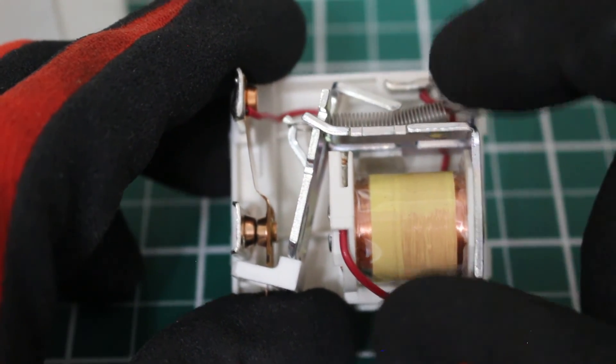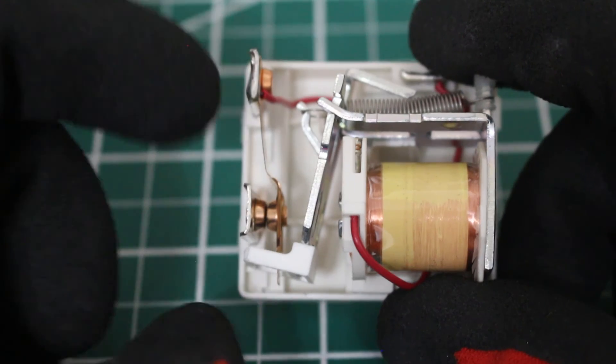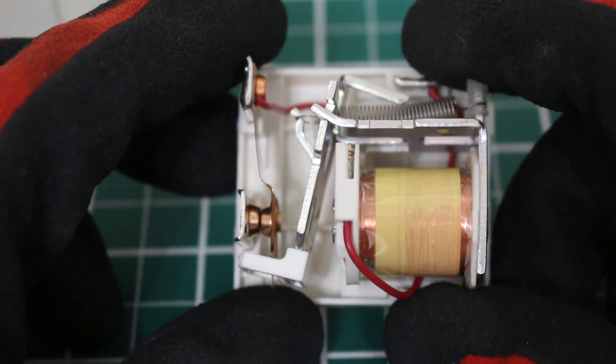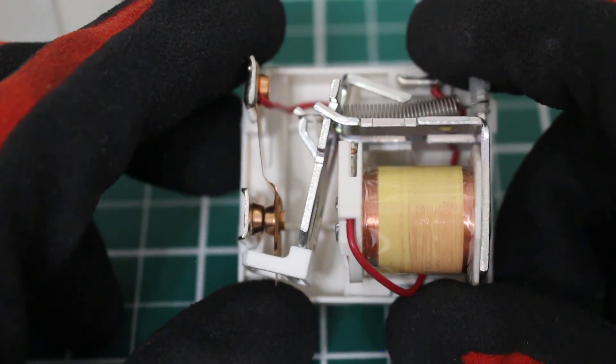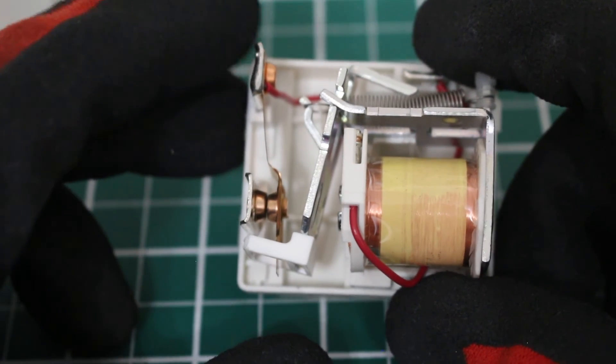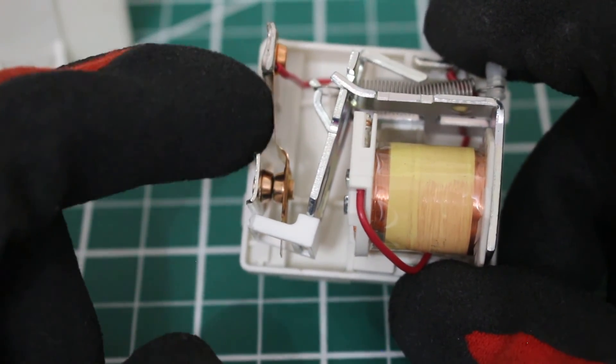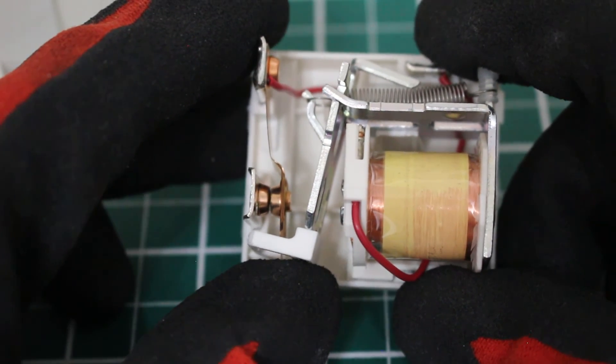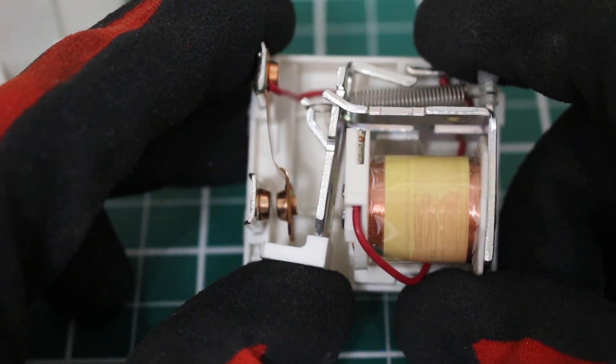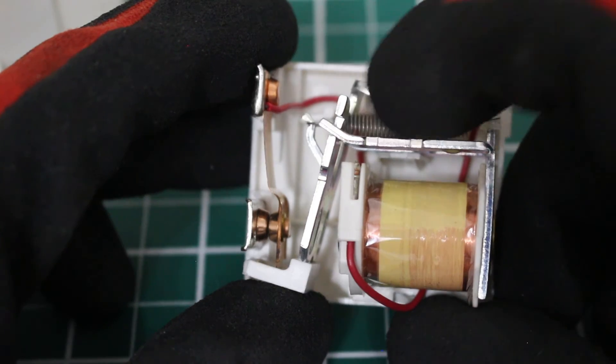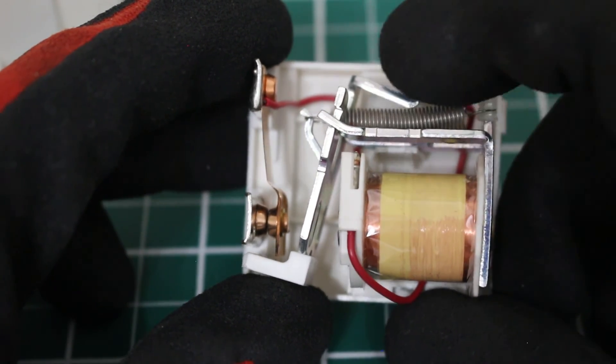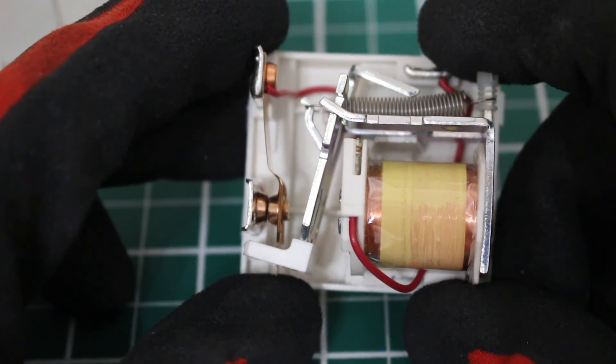So, voltage is going to flow through the coil. These contacts are closed, it's going to head to our start cap. Once we're up to speed, we're going to get that EMF, that back EMF. It's going to travel back. And then it's going to open the contacts once that force overcomes the tension of this spring.